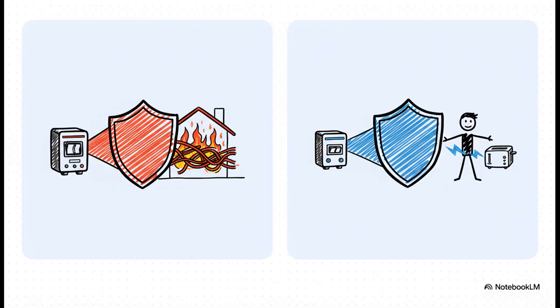Let's put this side by side, because this is really the core of what you need to know. The circuit breaker protects wires from big faults to stop fires. The RCD protects people from small leaks to stop electrocution. They have two totally different jobs, they are two different devices, and they are not interchangeable.